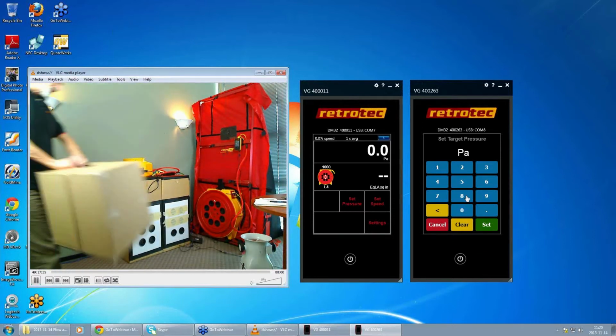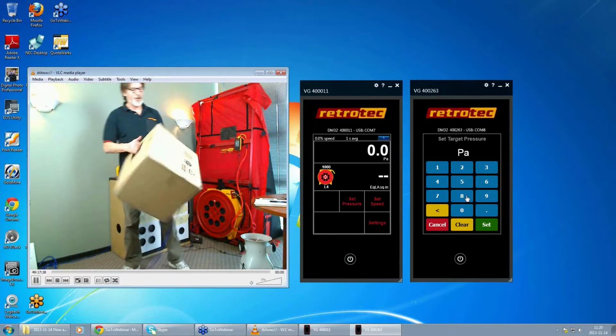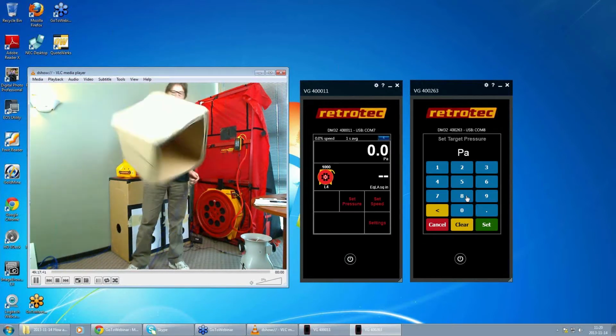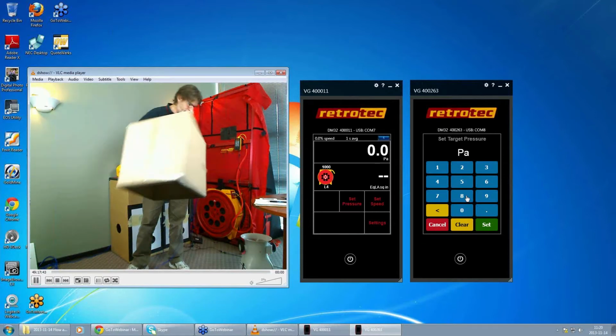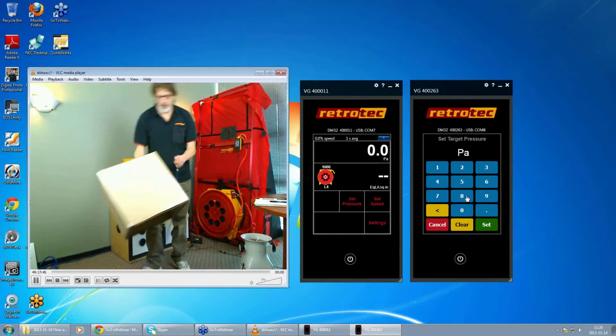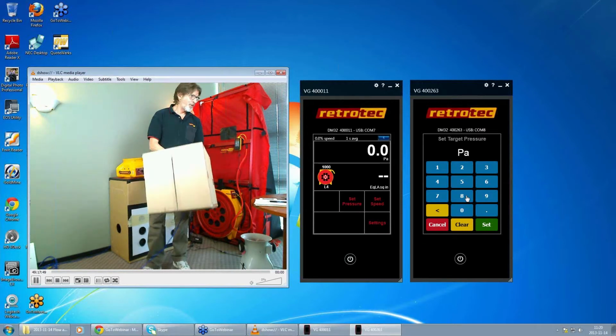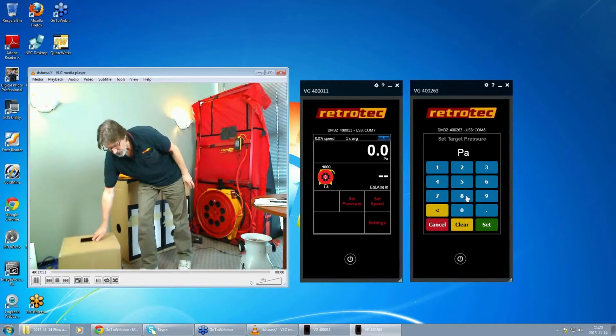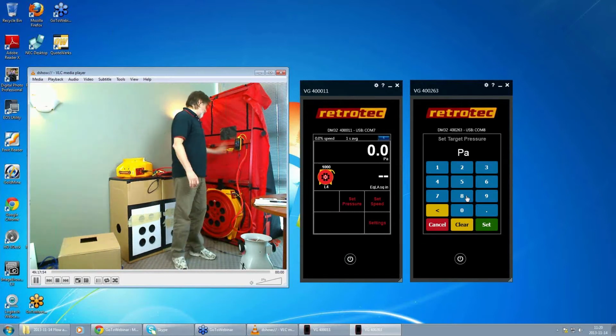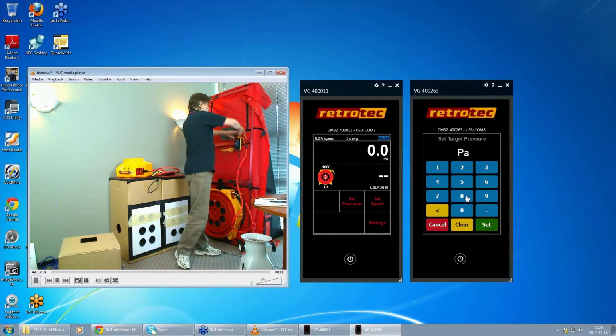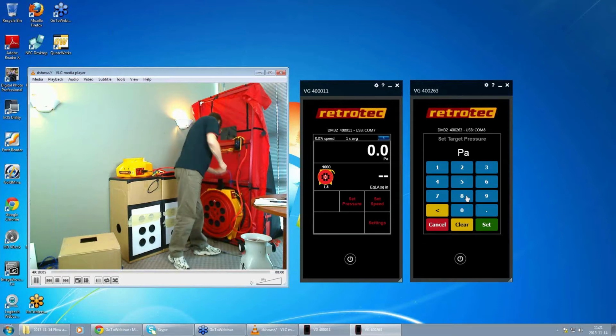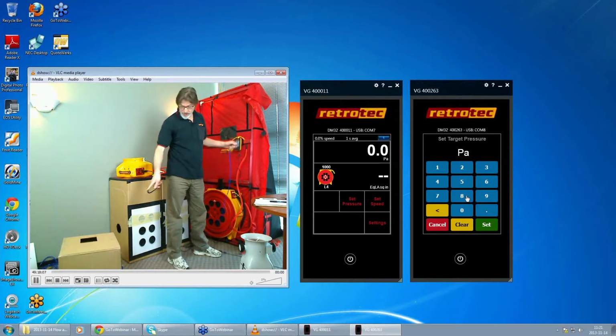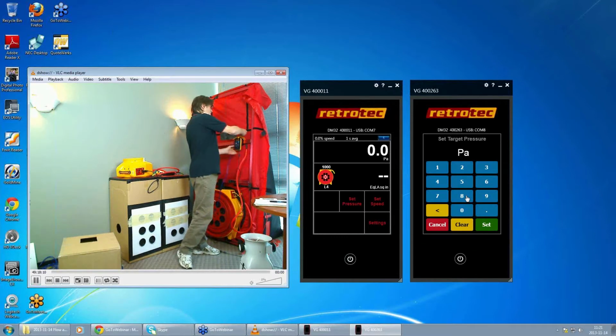The flow through this hole is proportional to the area of the hole. So we're going to use this in order to measure flow. All we need to do is measure the pressure inside the box, use hole flow on our gauge, and that will give us flow. So we go back to our gauge, and in this case we are not going to use this on the blower door at all, so we'll just disconnect these here. And we're going to take this blue tube, which is connected to that blue tube, and put it on the flow side. It should actually be yellow, but it doesn't really matter as long as you've got it hooked up in the right place.